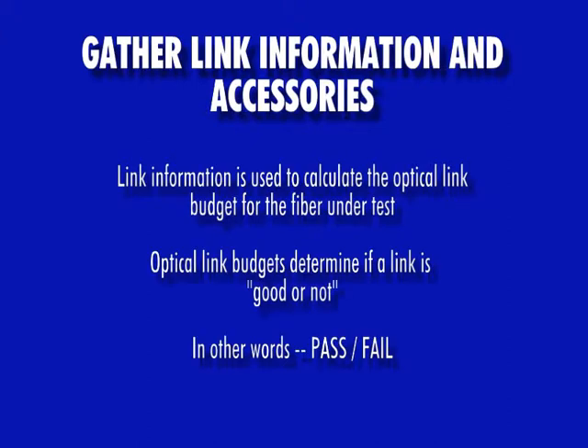Before beginning any fiber test, the user must gather the necessary link information and accessories required to complete the test. Link information is used to help determine how much loss is acceptable for the fiber under test, otherwise known as a link budget. Optical loss measurements are compared to the link budget to determine if the fiber passes or fails.